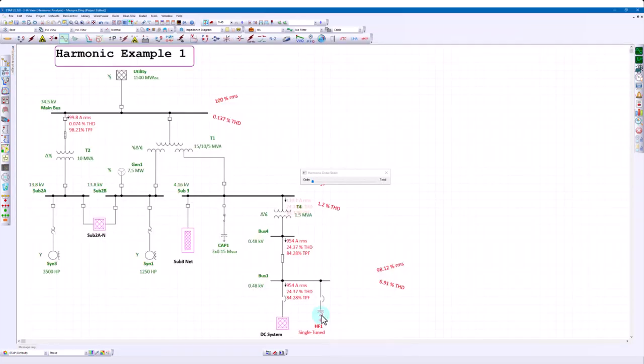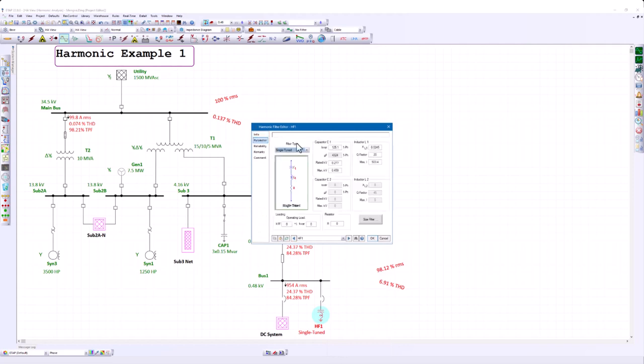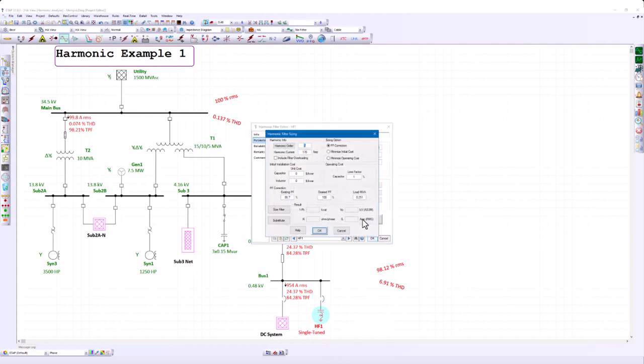Let's take a look at the harmonic filter editor. We go to the parameter page and click on the size filter. In order to size the filter, we need the harmonic order we would like to eliminate, which is 5, and the harmonic current at fifth order, which I have checked and entered as 170. For the sizing option, we select the power factor correction. My desired power factor is 100%, so we still need to find the existing power factor and also the load MVA. So let's see how I'm able to find the existing power factor.